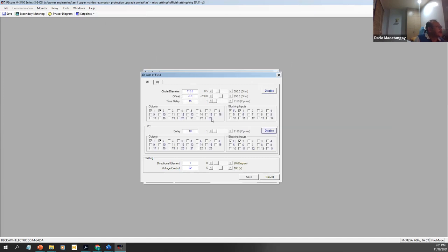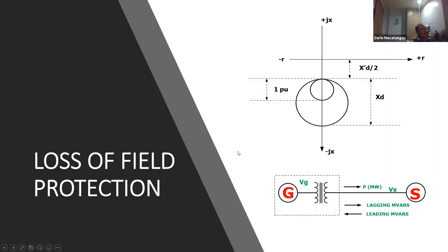Here you can see the set points. Circle diameter, zone 1, 113 ohms, offset minus 9.1 ohms, time delay 15 cycles. Under zone 2, 240 ohms and 30 cycles. And then it tells you what the outputs of the relay are. So that's a sample of the relay settings. Okay, so that's loss of field protection.